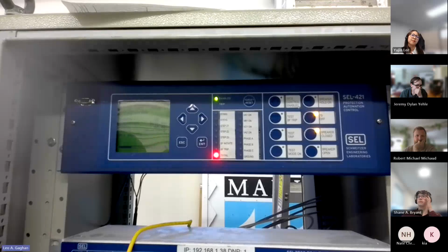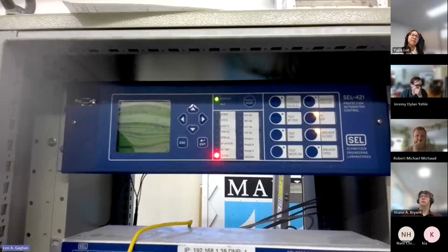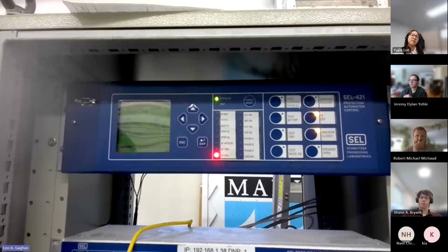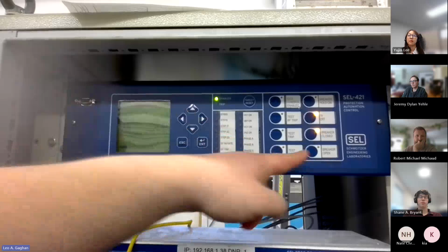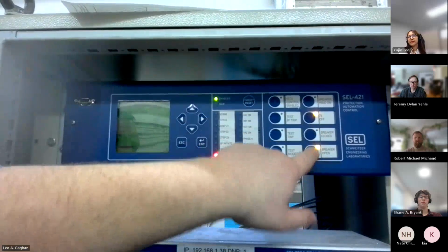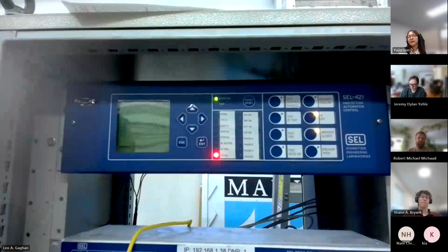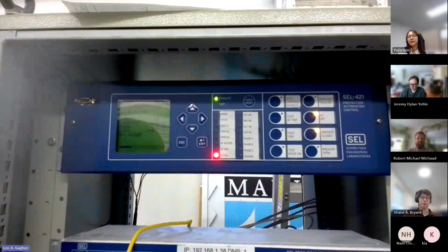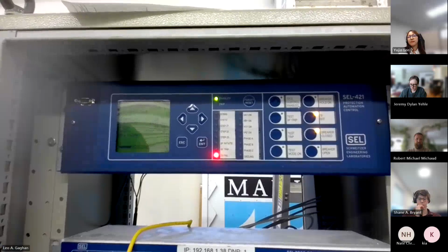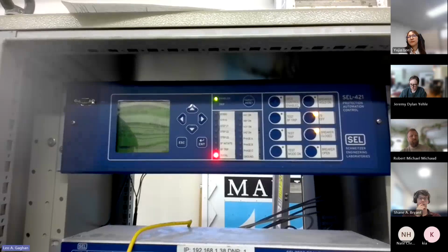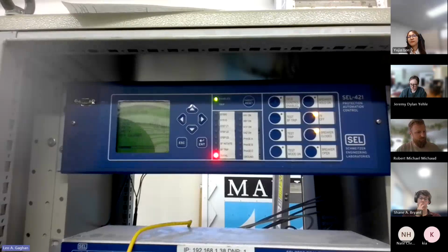And then some other logic on here. That's the LED that we talked about, right? We can see, you know, we close the breaker, the LED itself turns on. So we can see the programming for that LED is also good. And then we can see there on sheet 3, that's also good.